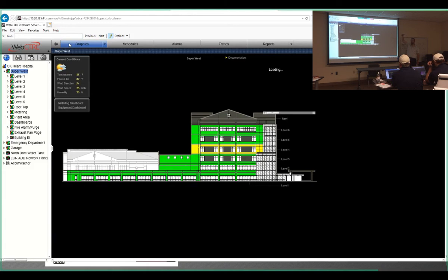So it maintains that. If somebody goes and cuts the comm cable, because the way we're controlling is all the VAVs tell the air handling unit what to do, we lose that comm cable to all the VAVs. The air handling unit still runs, it maintains the static up there. It's like maintaining 3 inches of duct static up at the air handling unit. But down on the floor, we only had 1.5 inches. So we had the TAB guys go through with us and set those static pressure transducers.